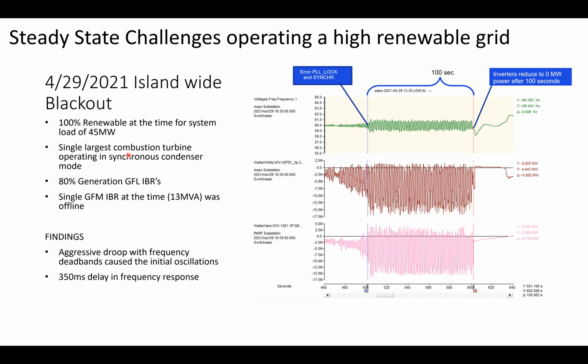We had our single largest combustion turbine operating in synchronous condensing mode. And at the time, 80% of our generation was from grid following IBRs. And then the single grid forming mode IBR that we had at the time was actually offline. So in a sense, we were trying to control the grid strictly with grid following inverters and the remaining synchronous machines that we had online, which was at 20%.